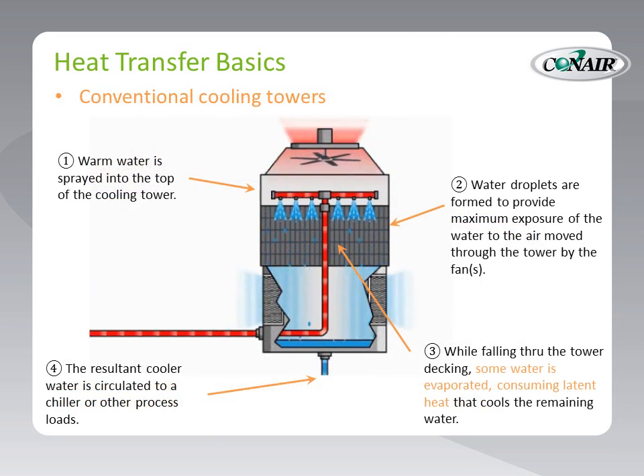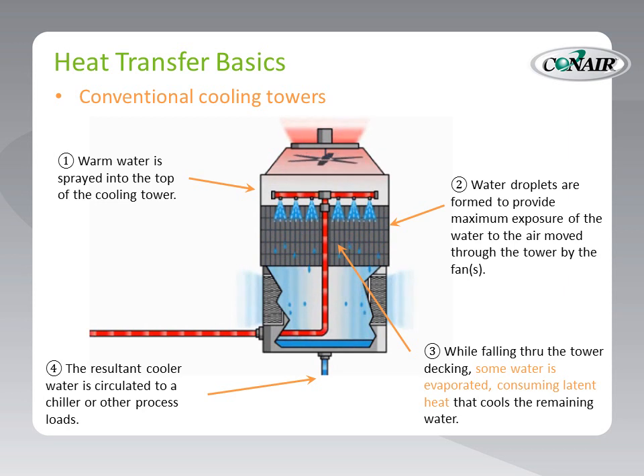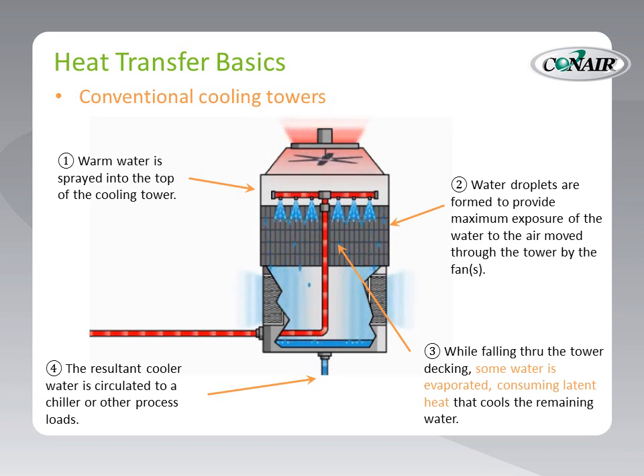Evaporative cooling towers take advantage of this to cool process water. As warm water is introduced into the top of the cooling tower, it falls in droplets through the tower decking. The cooling tower fan circulates air across those droplets, evaporating a portion of the water. The latent energy required for that evaporation cools the remaining water, which is collected at the bottom of the tower and is circulated to the process loads.